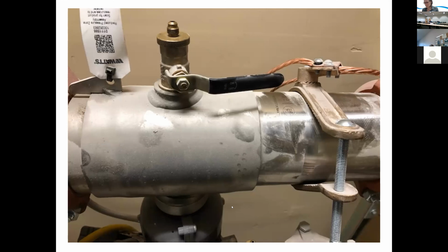You'll also see that they'll put in a weight support. So they'll put the support bar right underneath the sleeve, so that when the backflow assembly tester has to come in and repair this backflow assembly, they have to jump through hoops to try to slide this sleeve over in order to make repairs inside.